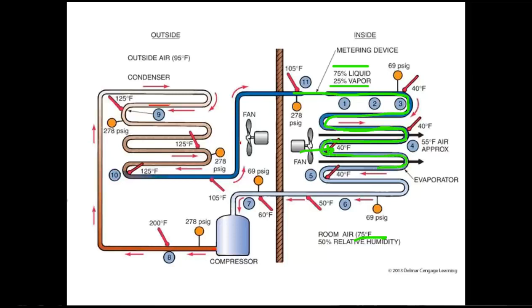So we are changing state all the way through the evaporator coil till we hit the certain point which is designed by the engineers. All of the refrigerant is boiled off, and we are now 100% vapor, and any heat that is picked up doesn't really cool anything, but it does ensure that we have 100% vapor heading back to the compressor. So we have superheated vapor coming back to the compressor.